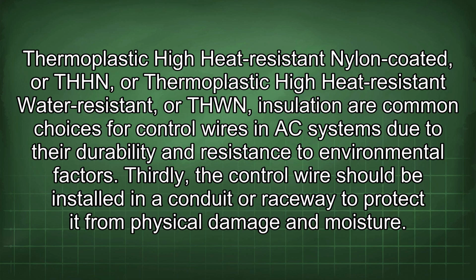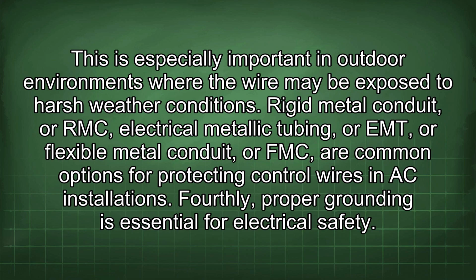Thirdly, the control wire should be installed in a conduit or raceway to protect it from physical damage and moisture. This is especially important in outdoor environments where the wire may be exposed to harsh weather conditions. Rigid metal conduit, or RMC, electrical metallic tubing, or EMT, or flexible metal conduit, or FMC, are common options for protecting control wires in AC installations.